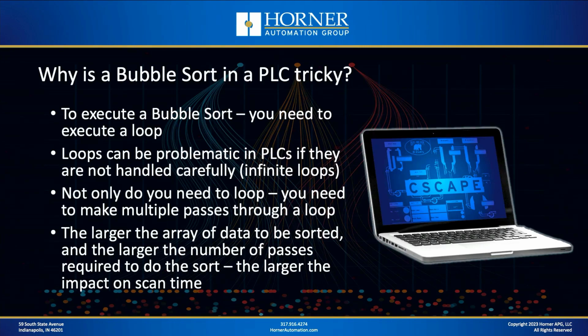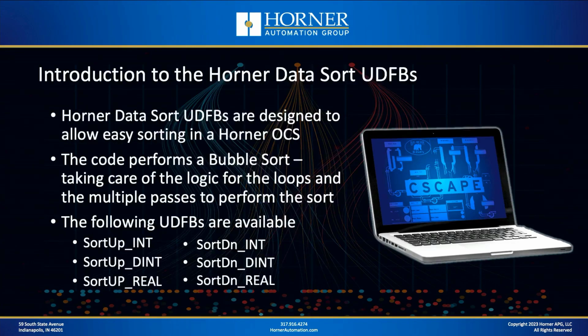If they're not handled carefully, you can end up with an infinite loop. And not only is it tricky because you need to loop, but because you need to make multiple passes through a loop. So the larger the amount of data, or the larger the array you need to sort, and the larger the number of passes that you need to go through the data to accomplish the sort, it can also have an impact on scan time. So in some scenarios, you'll find data sort routines in PLCs which are limited to a certain number of passes per scan. In our case, we're going to limit it to a certain size of an array to keep it from going off the rails, if you will.